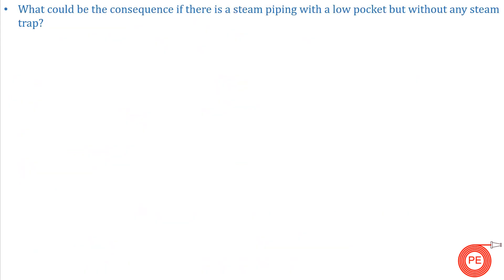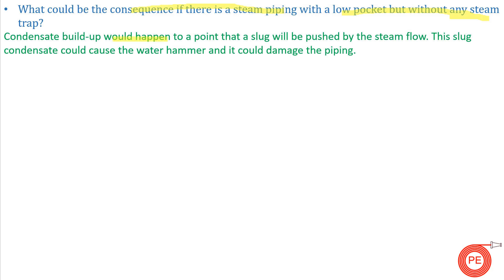Next question: what could be the consequences if there is steam piping with a low pocket but without any steam trap? Condensate buildup will happen to a point where slugs are pushed by the steam flow. This slug condensate can cause water hammer and damage the piping. That's why a steam trap is required at low points in steam pipelines to remove condensate.